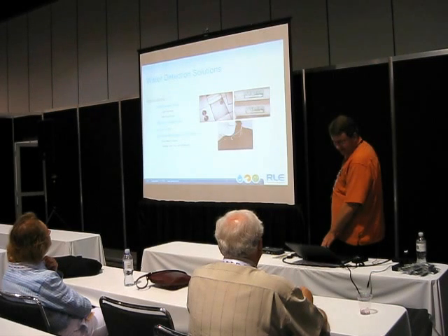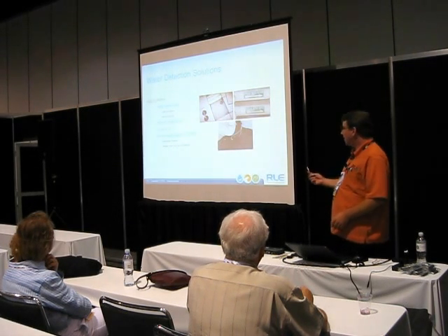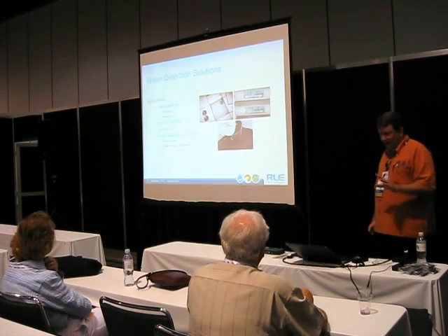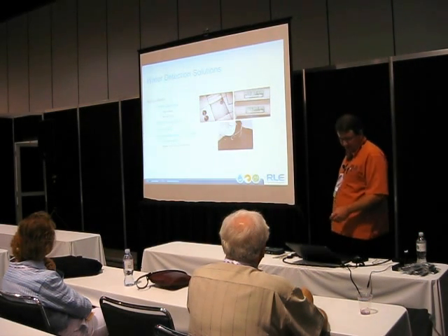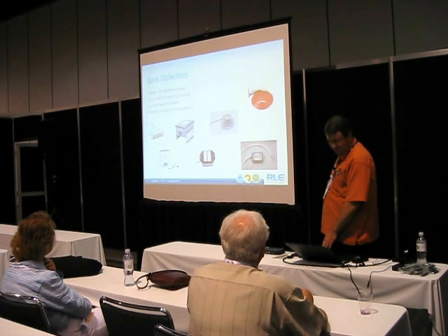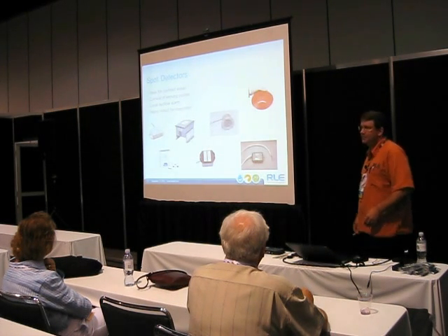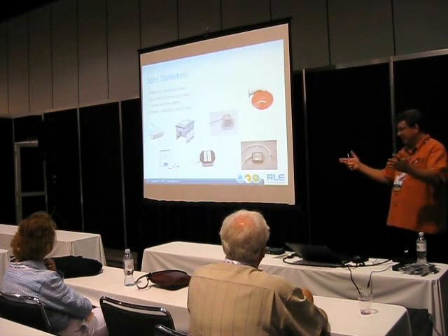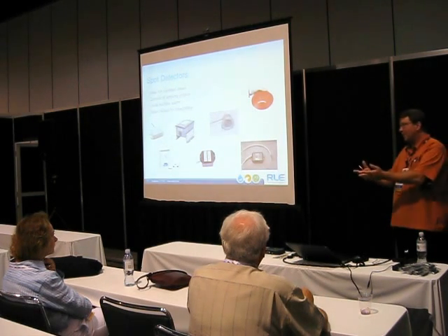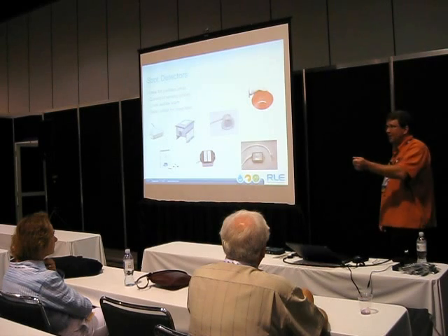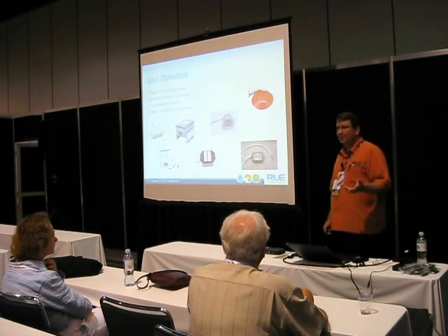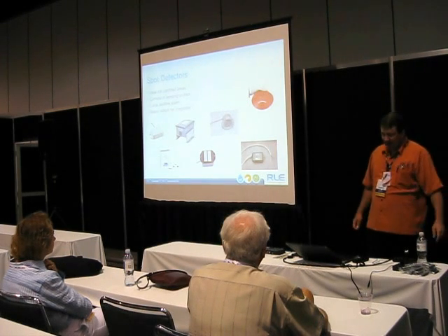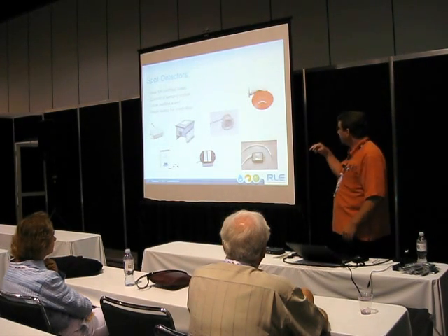You have a few different applications with leak detection: under raised floors, fixed to water lines, in drip pans, or actually encapsulating areas of concern, and I'll touch on that as I get into the systems that are there. Spot detectors, no question, are only good for a confined area. A small area that's basically a dammed area where water has nowhere to go except that single point. I've seen people try to use spot detectors on the floor. Murphy's Law will always take place and the water's going to roll right around. You'll never catch it. But generally they consist of a couple of probes sticking down.